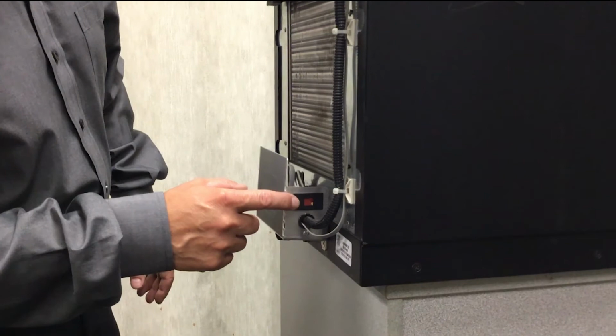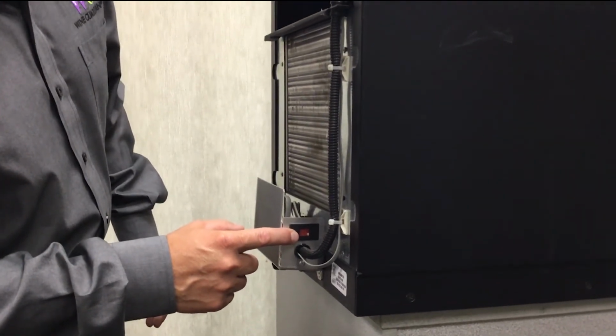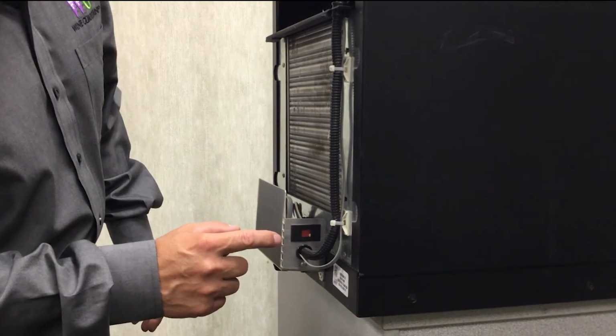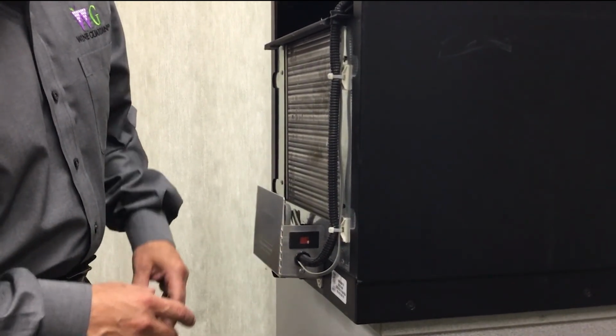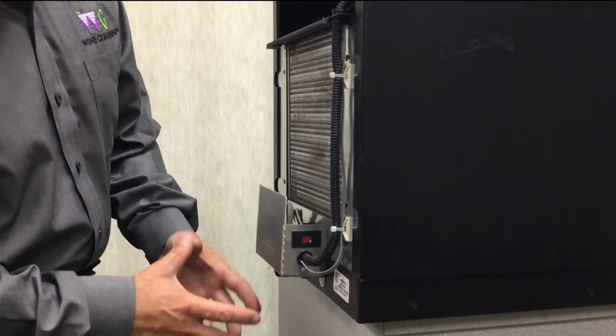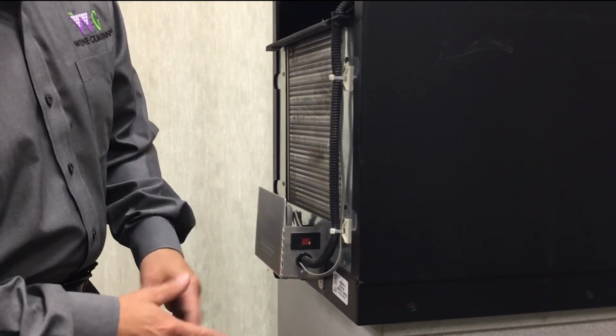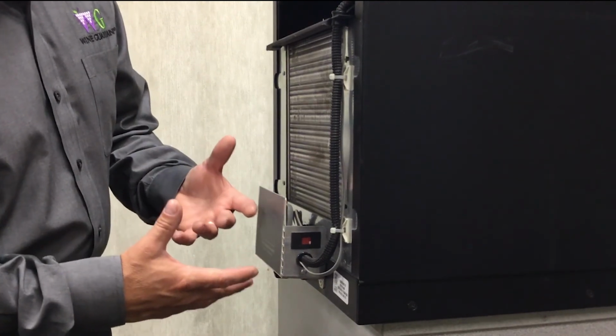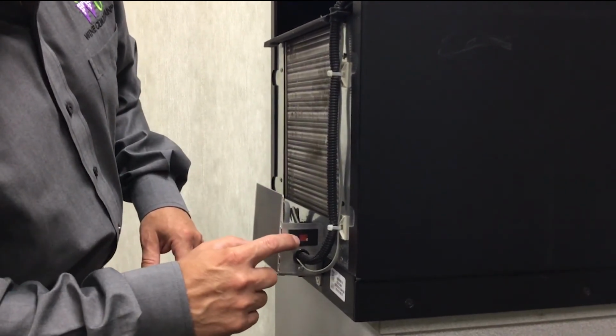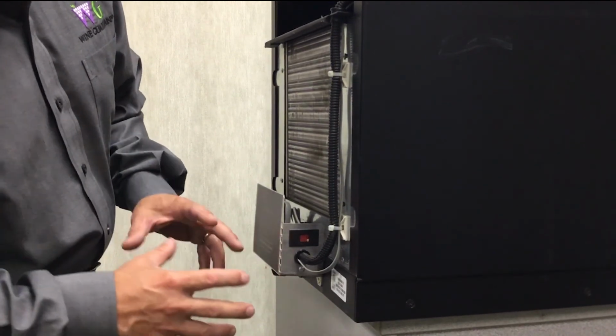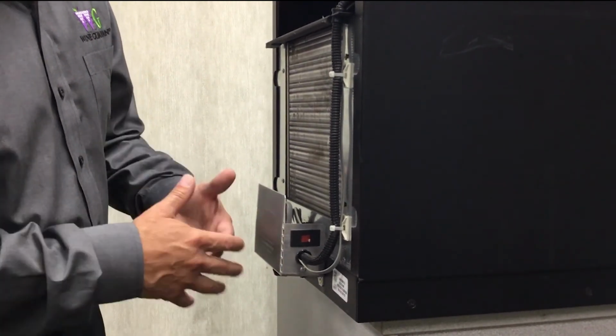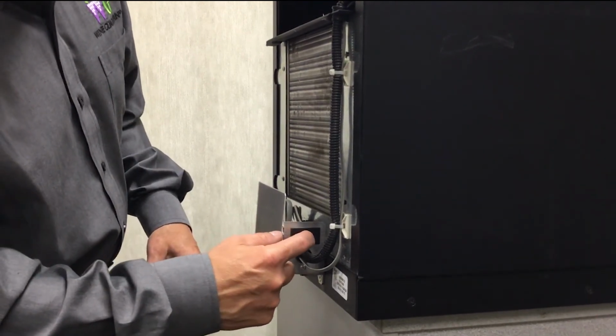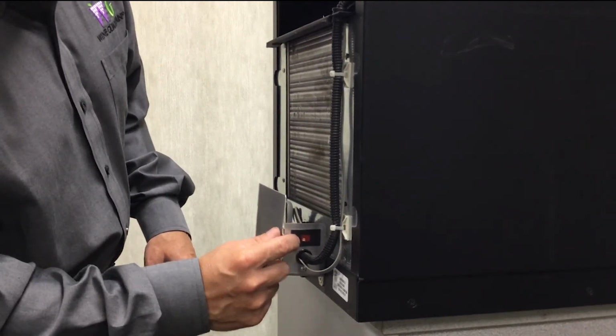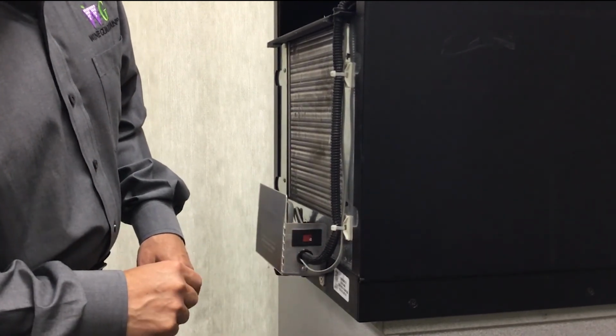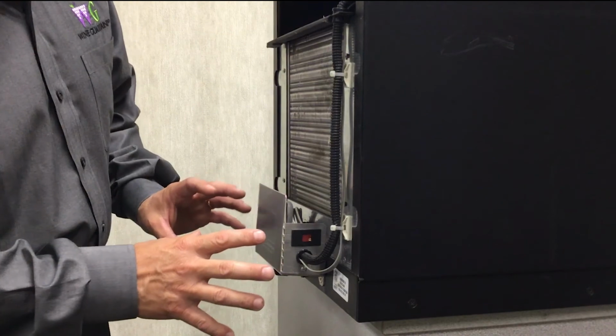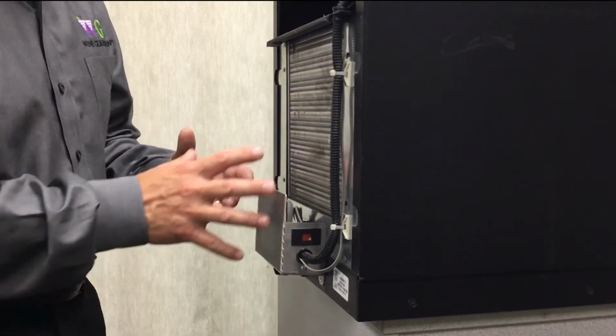One other key element to the condenser side is the power cord placement switch. As I mentioned, it comes standard equipment on the condenser or warm air section of the unit. In order to move it to the front of the unit or the wine room side, you have to flip this red switch here to move the power from the condenser side to the wine room side. So it's a matter of moving the switch over. You can see I just did it there, and back to the other side of the unit. So that's a requirement for you to move power from one end of the unit to the other end.